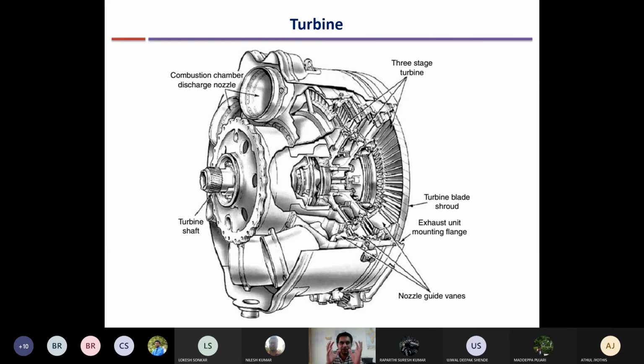The main distinguishing feature of a reaction turbine is that both the rotating part, the rotor blades similar to a compressor, and the static blades, the stator, both act like nozzles. So both accelerate the flow, and there is expansion in both of them.